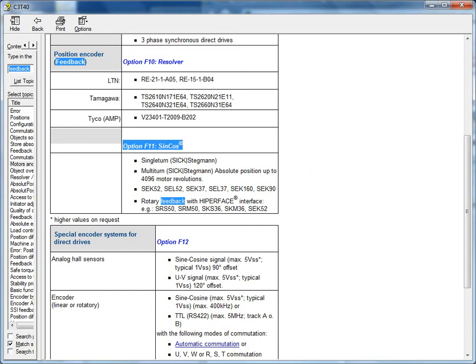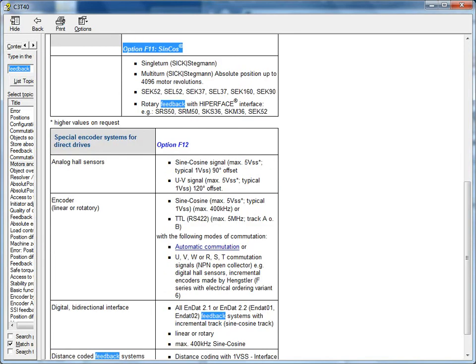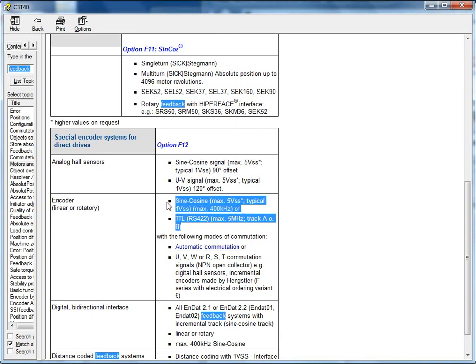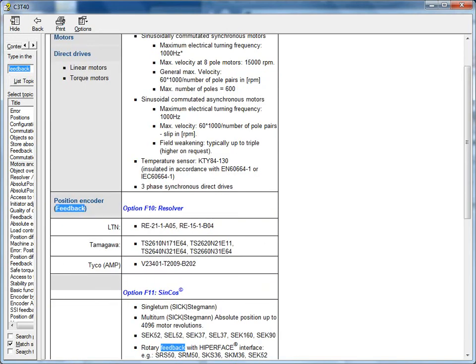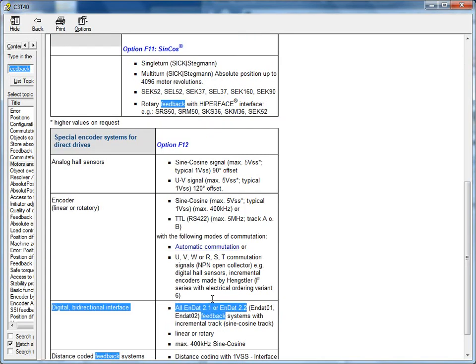The F12 supports the analog hall sensors, sine-cosine, 1-volt peak-to-peak incremental encoders, and then also the quadrature TTL encoders. The F12 also supports the EnDat 2.1 and 2.2 absolute encoder types.